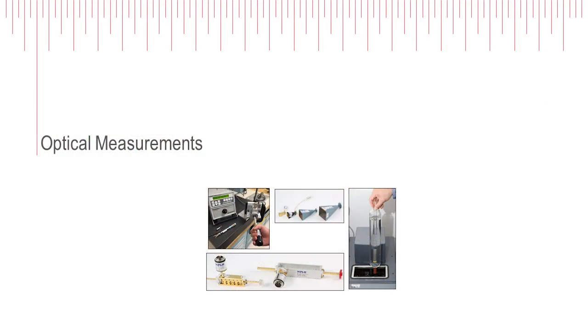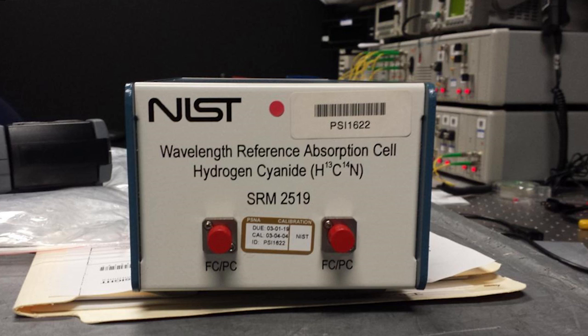Now I'm going to move to optical measurements. First, you're looking at a reference absorption cell. This is essentially a comb filter. So if you put a tunable laser in one end and then put the output into an optical spectrum analyzer, you can measure the wavelength and calibrate that optical spectrum analyzer to incredible accuracy.